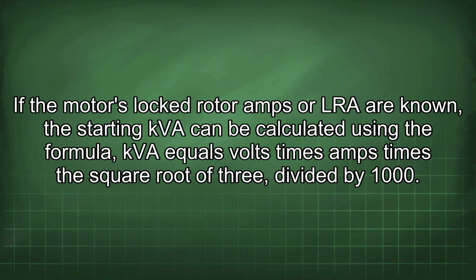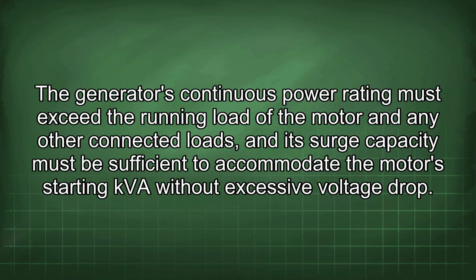If the motor's locked rotor amps, or LRA, are known, the starting kVA can be calculated using the formula kVA equals volts times amps times the square root of 3 divided by 1000. The generator's continuous power rating must exceed the running load of the motor and any other connected loads, and its surge capacity must be sufficient to accommodate the motor's starting kVA without excessive voltage drop.